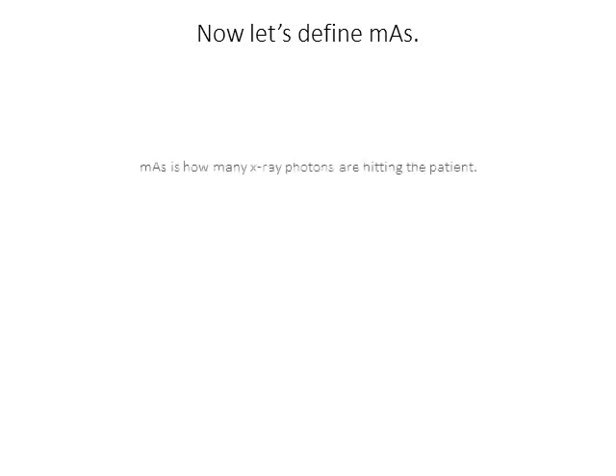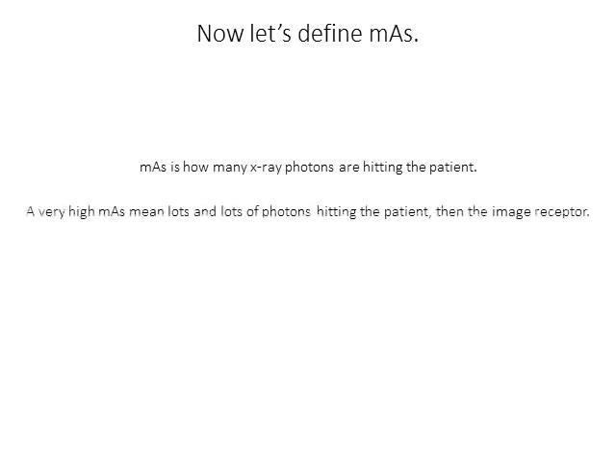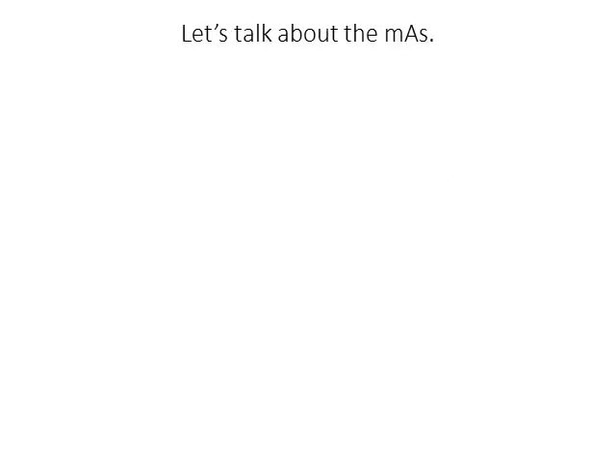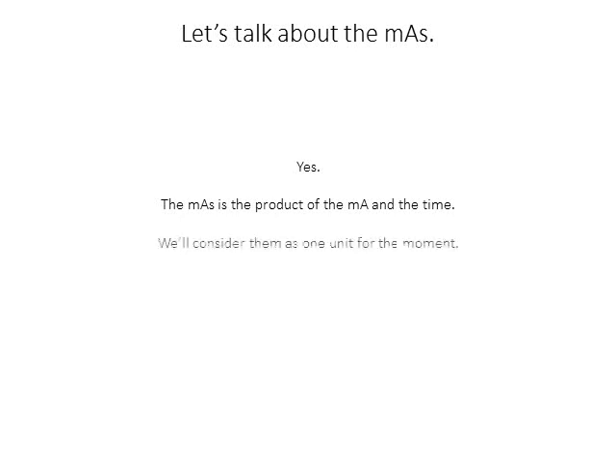MAS is quite literally just the number of photons hitting the patient — it's the product of the number of photons per unit of time multiplied by the time, that is the mA times the time. A very high MAS means lots of photons hitting the patient and then the image receptor. So the higher the MAS, the more photons hitting the image. Unless we have unusual circumstances, we're going to consider mA and time as one unit for the moment.